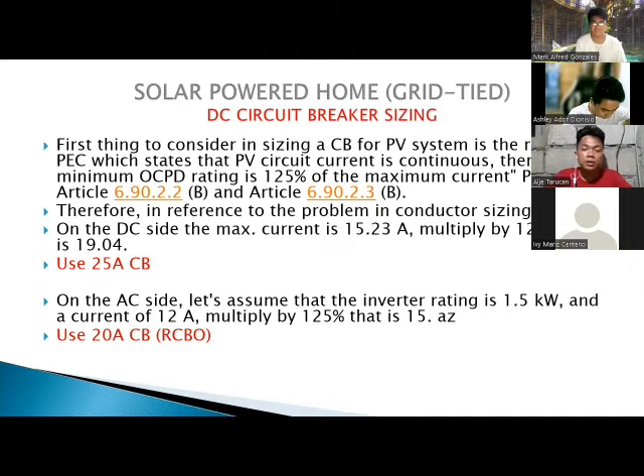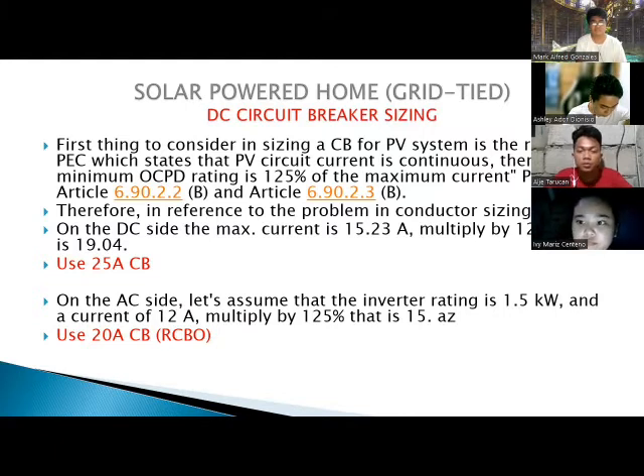On the DC side, the max current is 15.23 amperes. Multiply by 125%, that is 19.04. Use a 25 ampere circuit breaker. On the AC side, let's assume the inverter rating is 1.5 kilowatts and the current is 12 amperes. Multiply by 125%, that is 15. Use a 20 ampere circuit breaker, RCBO type.